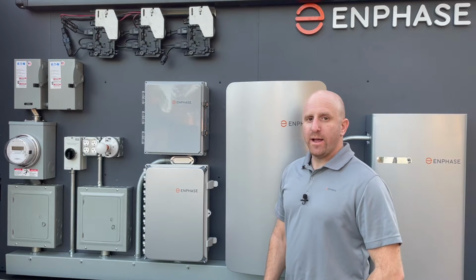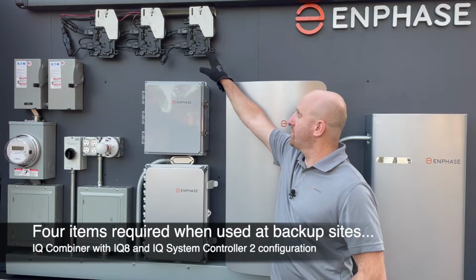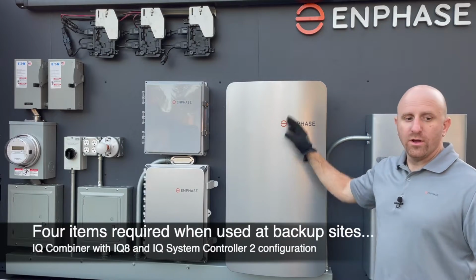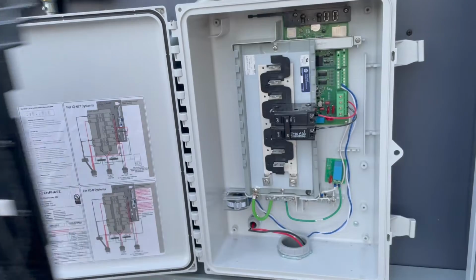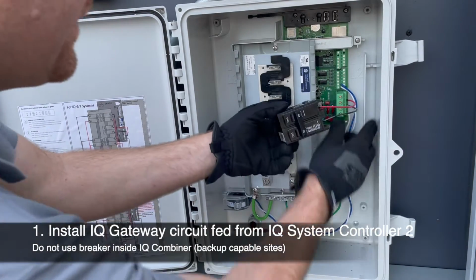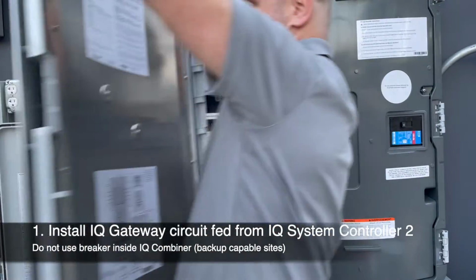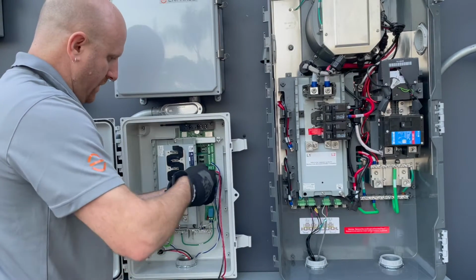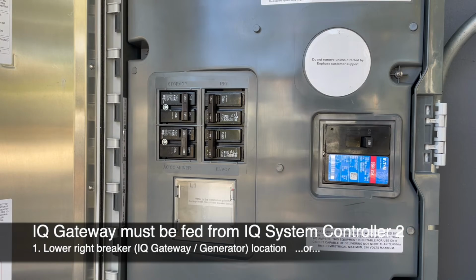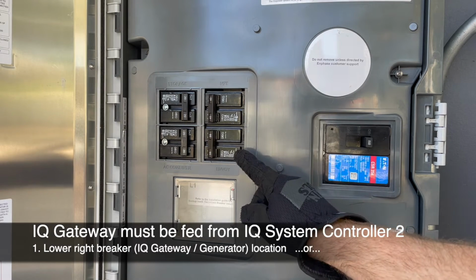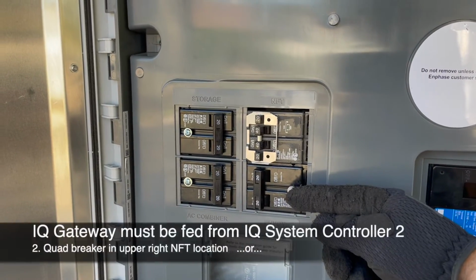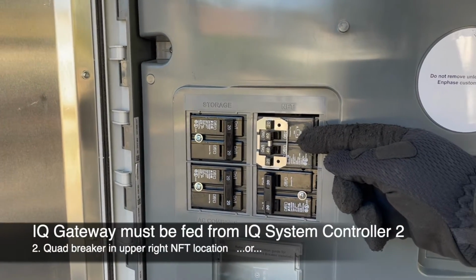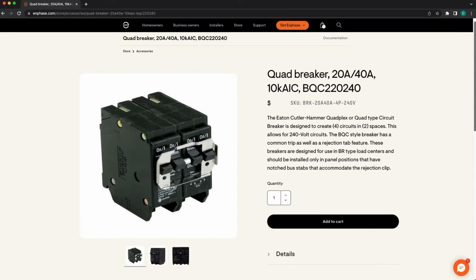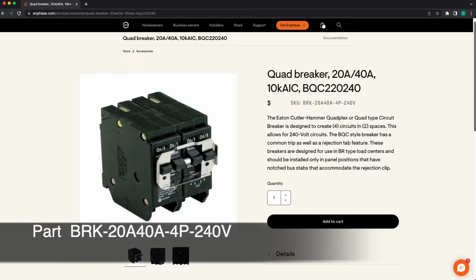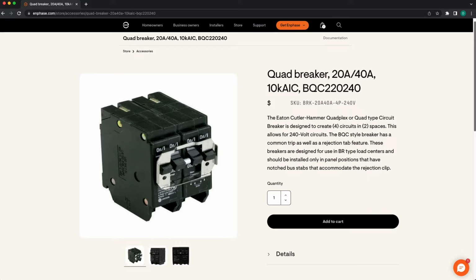If the site includes backup capabilities with IQ8 microinverters and an IQ system controller, 4 items are needed. You will need to install a new circuit for the IQ Gateway wired to the IQ system controller. Specifically, you will connect the IQ Gateway L1 and L2 terminals to one of 3 breaker locations, typically the lower right location. Or if a generator is installed here, you can use a quad breaker installed in the upper right breaker location. If you can't source them locally, quad breakers are available in the Enphase store online.